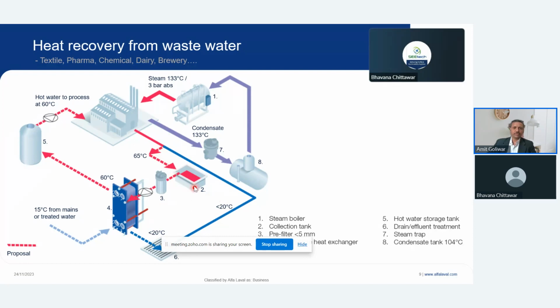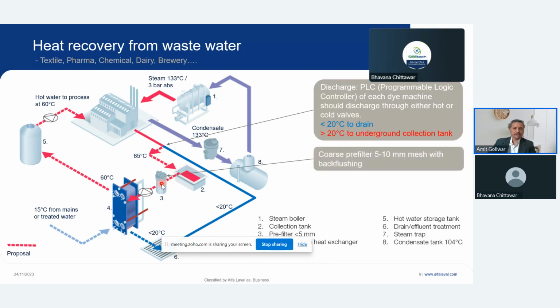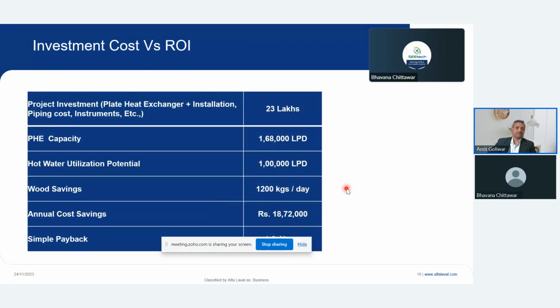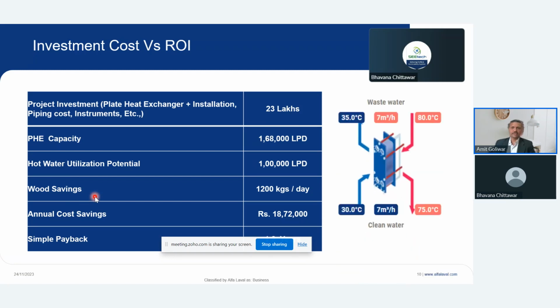What we propose is, before cooling it, take it separately, put it in a tank, put a filter, and then from the filter we can use the heat at least to preheat either boiler feed water or even the process water. In fact, many a time, if we reduce the water temperature, the same water can be circulated, so we can achieve water saving too. We have done a few projects like this, and one sample project gave us a very attractive ROI. This is a typical textile plant where the recovered heat is used for boiler feed water for generating steam, with very attractive payback, with duty conditions of 7 cubic meters per hour. While doing so, there are some challenges: if it is a fibrous fluid, then it is very difficult.